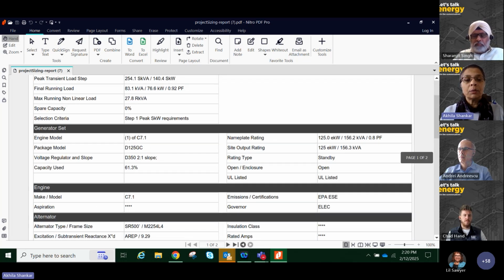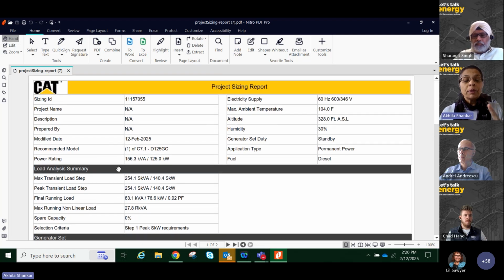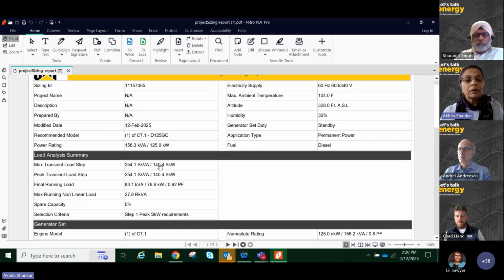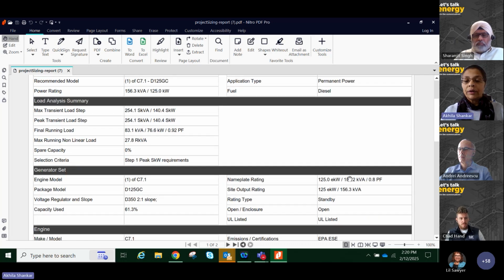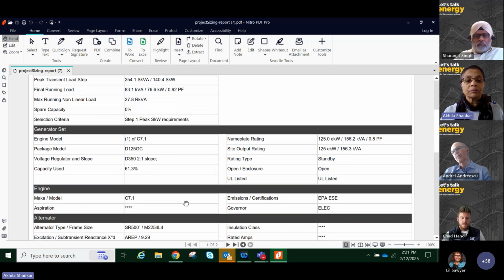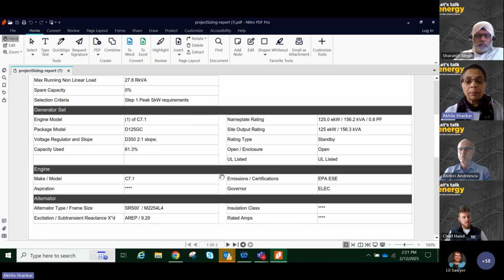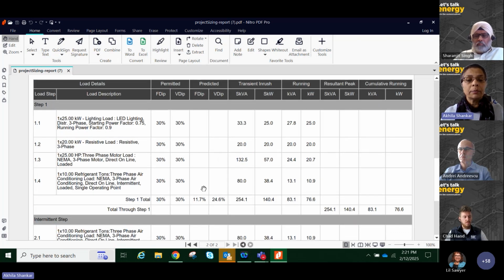So we see that it's a 125 kilowatt. Because I have not created an account, I've not been able to enter a project name. That's why this is showing as not available. But the recommended generator is shown here. It's a 125 kilowatt, a D125GC. You can also see that about 61.3% of the capacity of 125 kilowatts is used by the loads that I put in. So you have about 40% of future expansion capacity still available to you in this recommended unit.